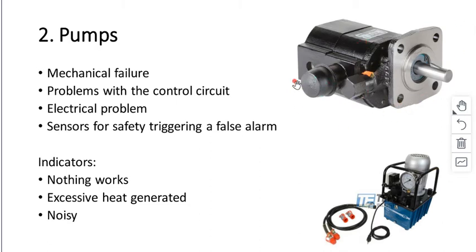We have got some stuff that is pumped in. So if there are some solids which got into the oil circuit and got into the pump, it might clog it up. So it could be contamination, or it could just be one of the other things. They're fairly sturdy, though, and fairly good. If pumps are getting noisy, that's normally an indicator that there may be a problem with the bearings. Once the bearings go, the seal is soon to follow, and it's time to change the pump.